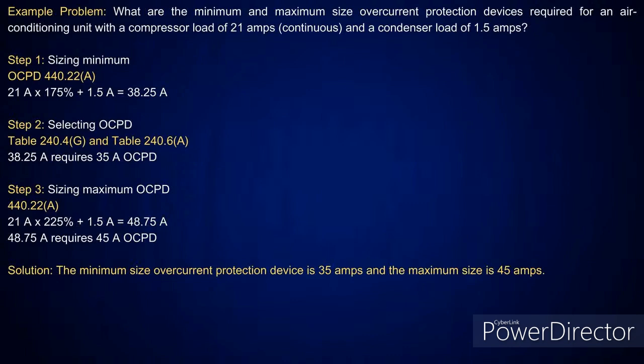Okay. Now I will tell you in the 2023 cycle, I've already added another step here. I've added step 3 that will pick up 440.22(A) Exception 1, and you'll be able to put a 40 amp there. Then I go down to the maximum size, which will be Exception 2, that says I can take it at 225%, but I won't exceed the calculated value again. So I take the 21 amps at 225%, add that 1.5 amp condenser on there. That gives me 48.75 amps. The next size below that's 45 amps. So this calculation is actually changed in the 2023. I would have a 35, 40, and 45 amps set there. Okay? Right. Because you need to be aware of that.